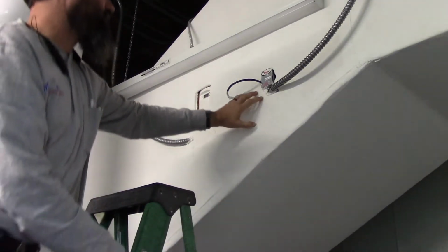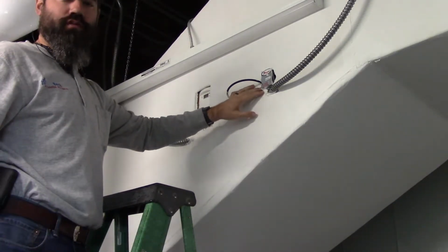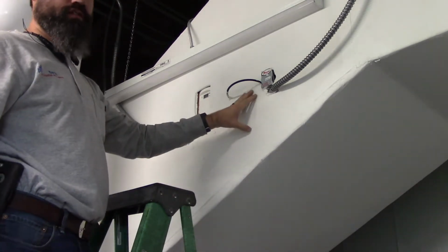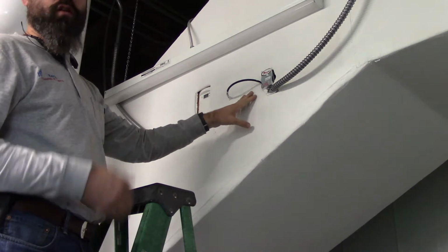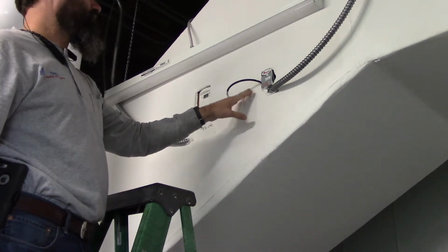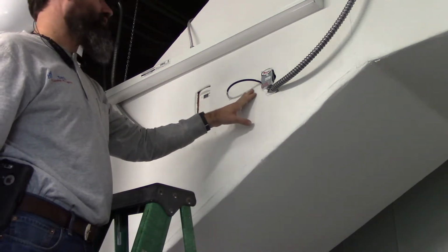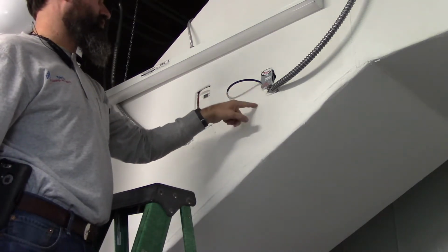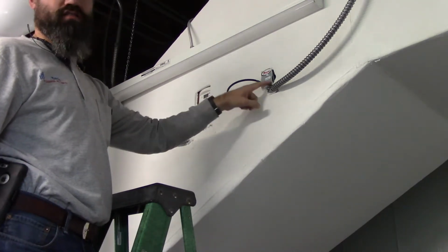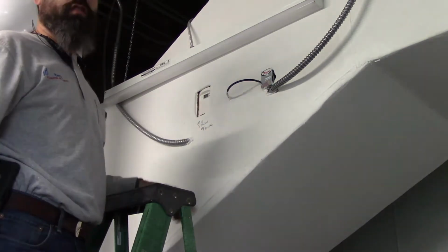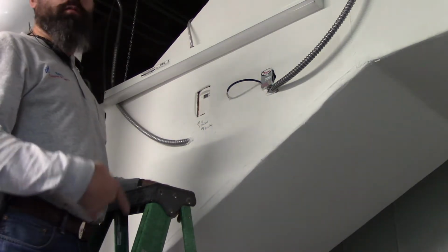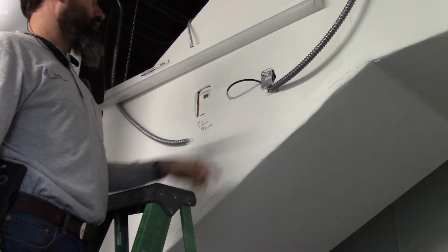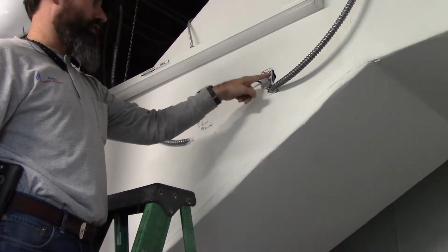This device here is a high pressure safety device. What it'll do is if you get a fire smoke damper or something that closes downstream of the unit, it's there to protect your duct, keep it from blowing out. So if you get a high pressure scenario inside this duct, this device is going to trip. It's got to shut the unit down. You'll get an alarm on the graphics, so it'll tell you that you've got a high pressure alarm. You have to push this button.